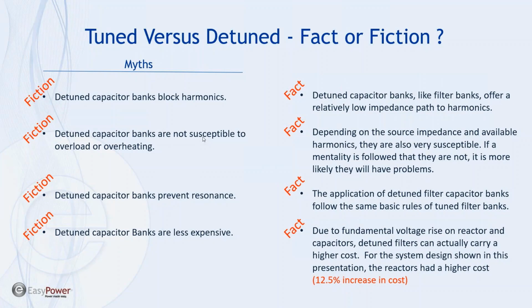Detuned capacitor banks are not susceptible to overloading or overheating. We already saw in the previous slides that detuned filters can also take in a significant amount of harmonics. So this statement is also fiction. Detuned capacitor banks prevent resonance. I didn't really show that in the slides, but like tuned filters, detuned filters experience the same exact issues. If you put a capacitor bank or you have cable capacitance in parallel with the filter, you're going to have resonance concerns. You must be concerned about resonance.